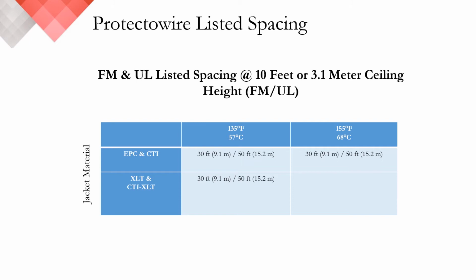For the intent of this presentation, we significantly reduced our listed spacing chart to only focus on our two lowest initiation temperatures, the 135 Fahrenheit, 57 Celsius, and the 155 degree Fahrenheit, 68 degrees Celsius detectors. Please remember that it is often necessary to reduce the detector spacing as the ceiling height increases.